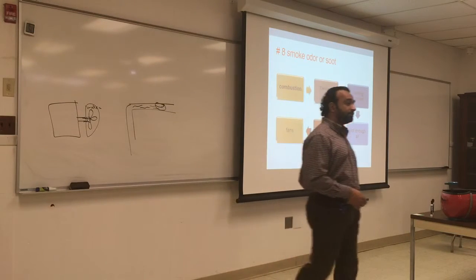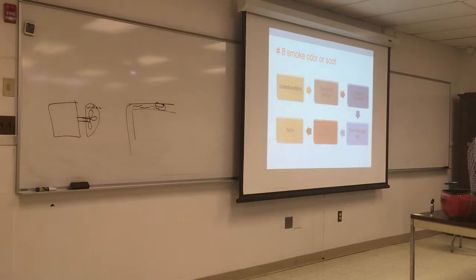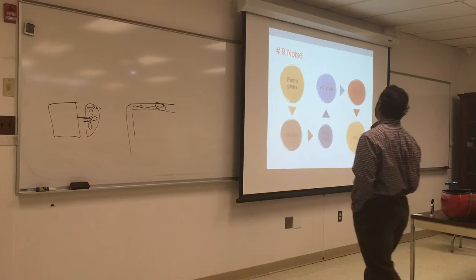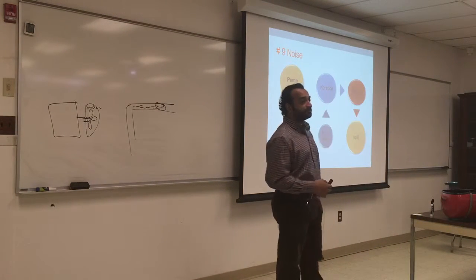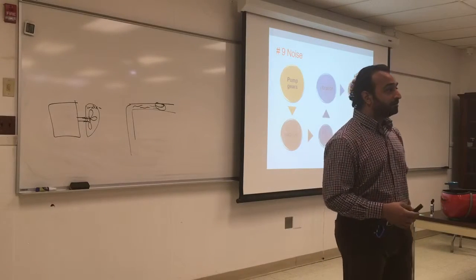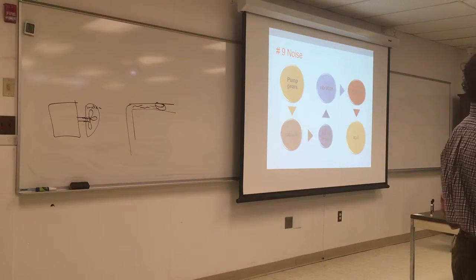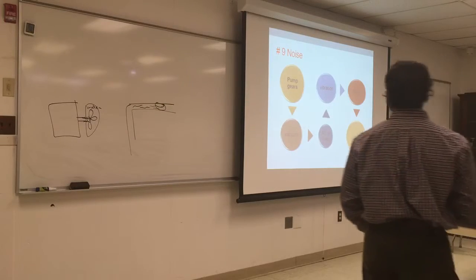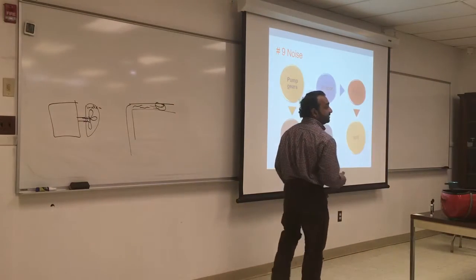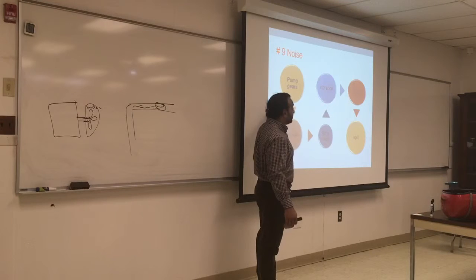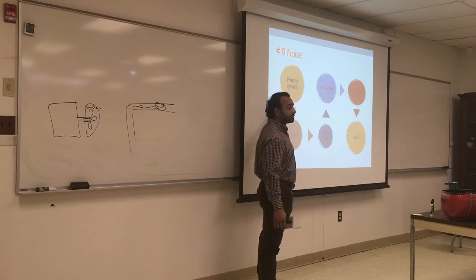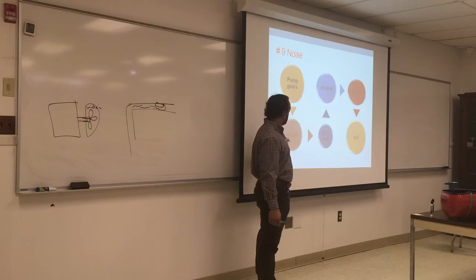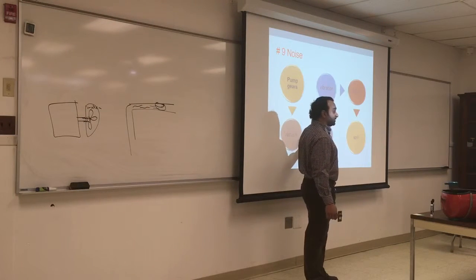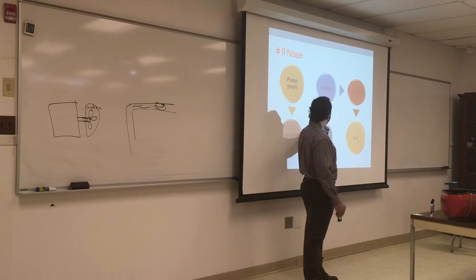Sometimes the fan gets burnt out, or they get something stuck in them, so check the fan is not giving off smoke. If you have noise, again, optimally the system should run smoothly, you should not hear any irregular noise. If you have any noise, it's gotta be something that's on the verge of breaking. Pump gears could be broken, impellers could be missing one of the fins. Vacuum. There's a vacuum in the line. Air in the line could cause a noise, a swishing noise.